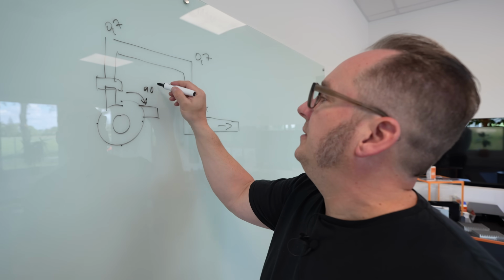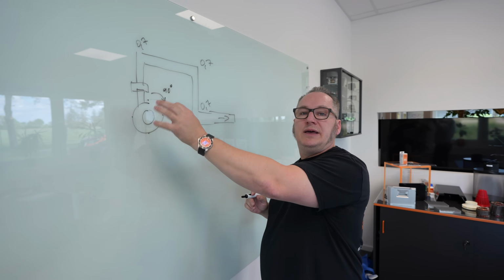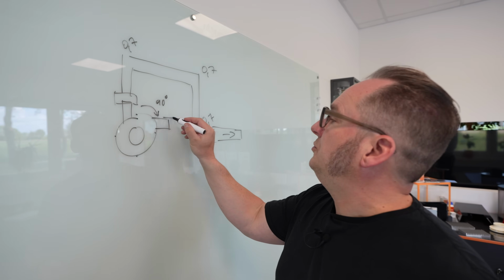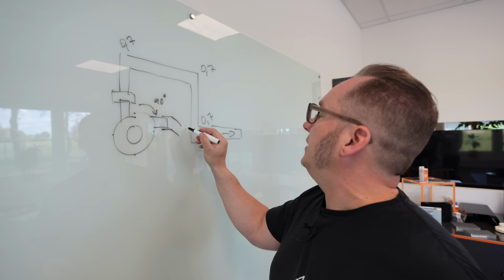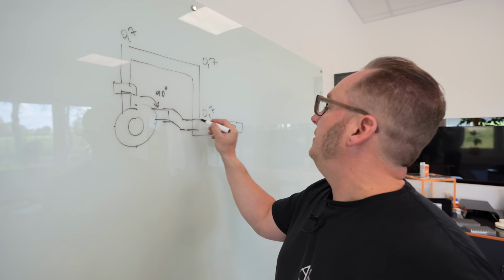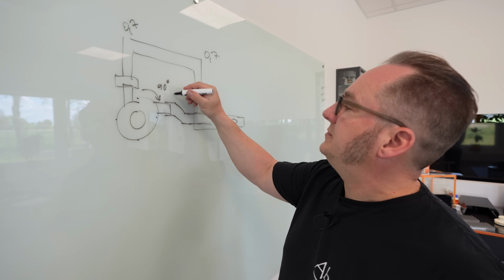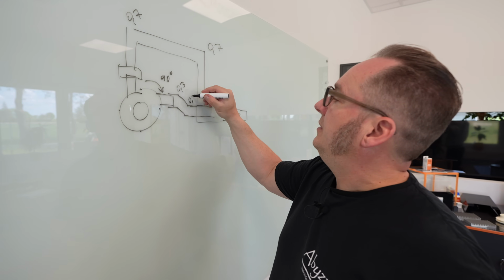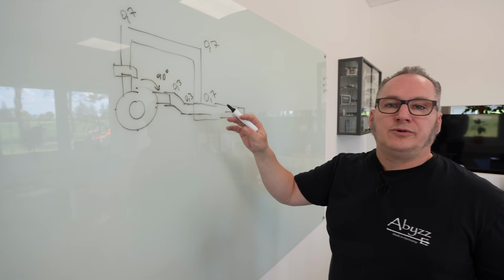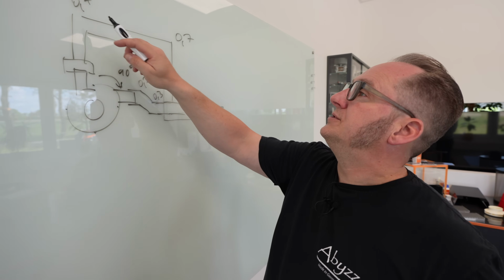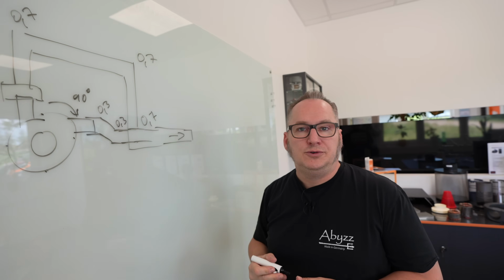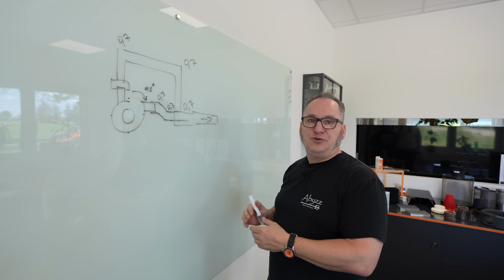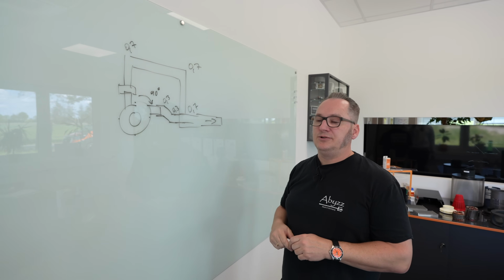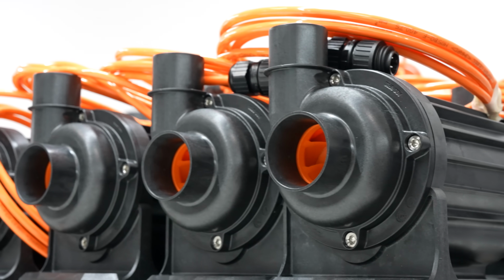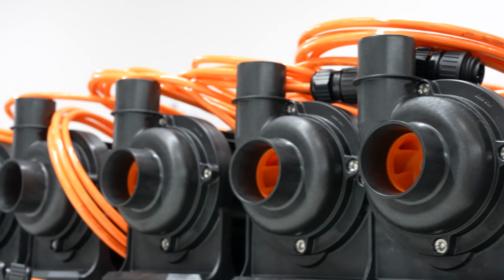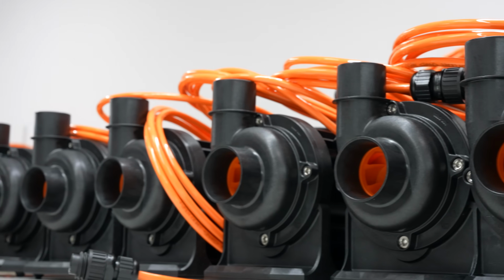So 90 degrees, which doesn't matter on this one whether you turn it, and then you could use 2 45s to actually reach the same level. And the 45s I think are at 0.3. So comparing these two, you're going from 0.6 in friction losses to 2.1 if you do the other way. So that's a significant difference, and that's why it's important to make those design considerations. Another thing which very often happens is that the pumps are completely plumbed wrong on the suction side.